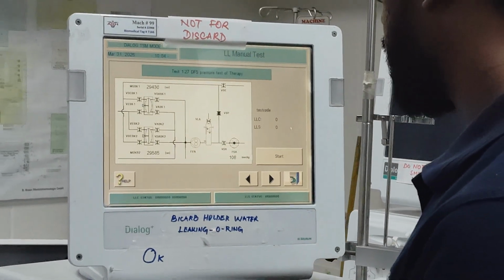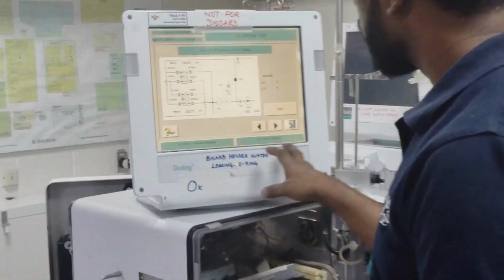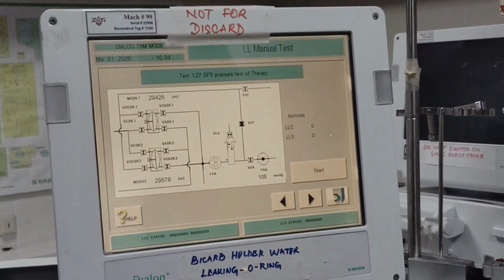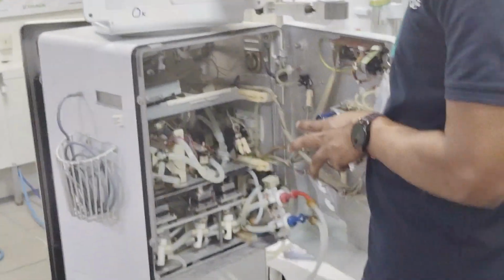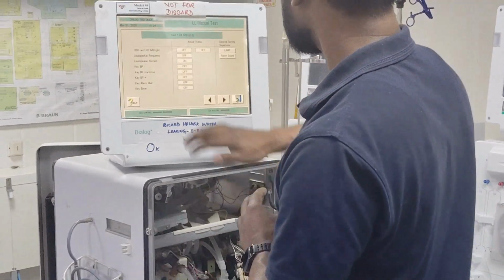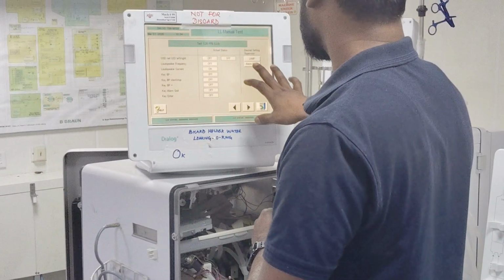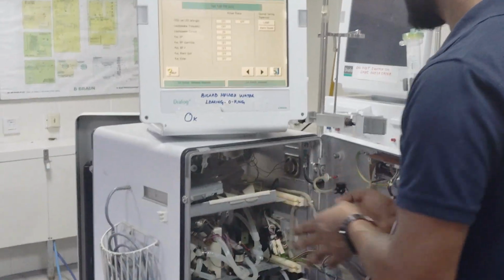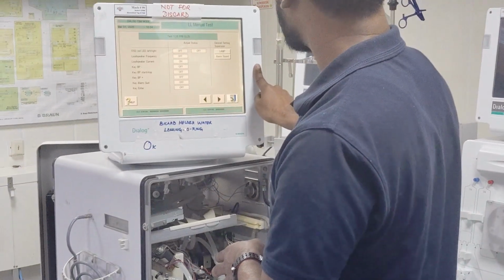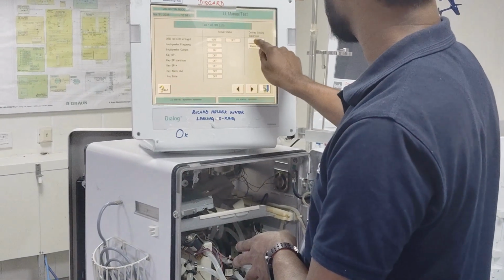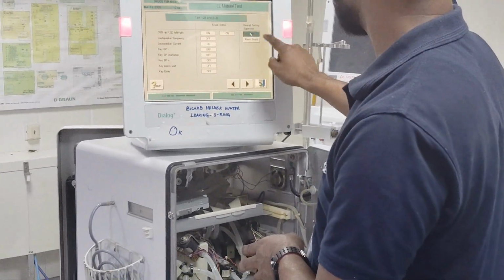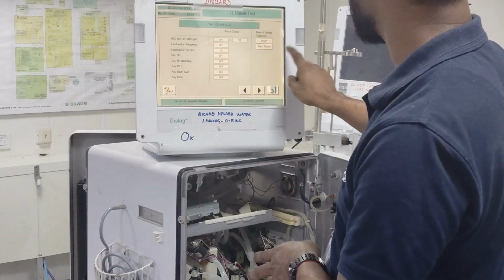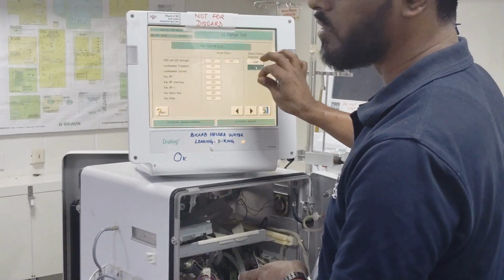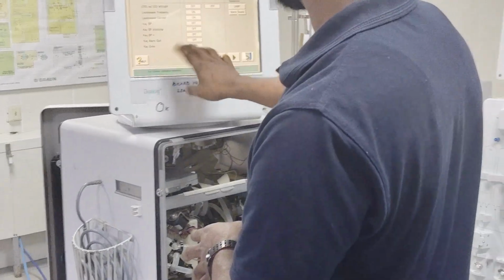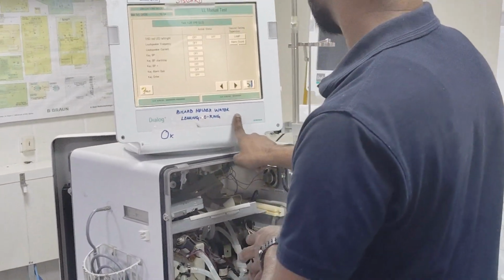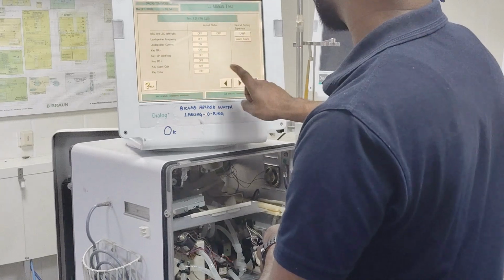When you face this problem during dialysis, in dialysis mode, you will get messages over there saying test not passing. So we have only done this testing here in test mode. Again, here at the LLS there are some boards and indication lights that we can check. We can check the lamp and the alarm. In this test mode, when we click this, the lamp will indicate. All the alarm systems are working, we can check them over there. The blood pump, the light, all these things we can check one by one here. All testing only.